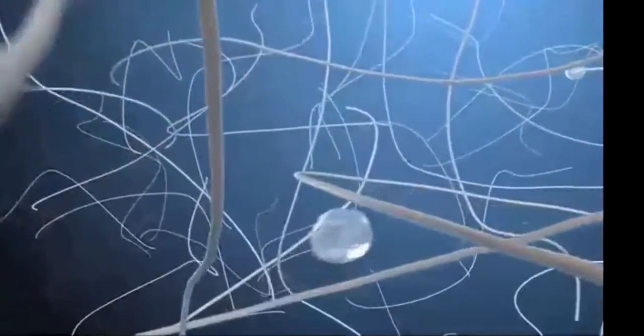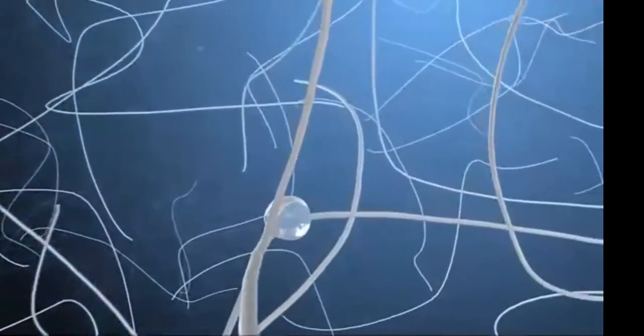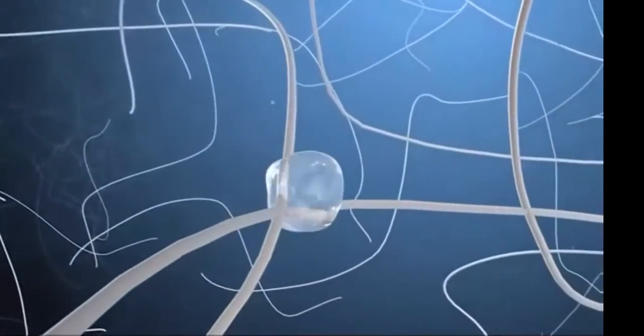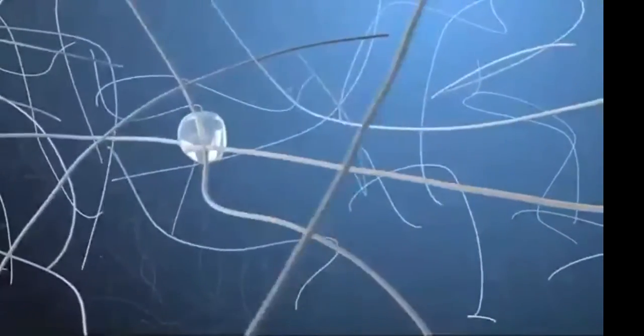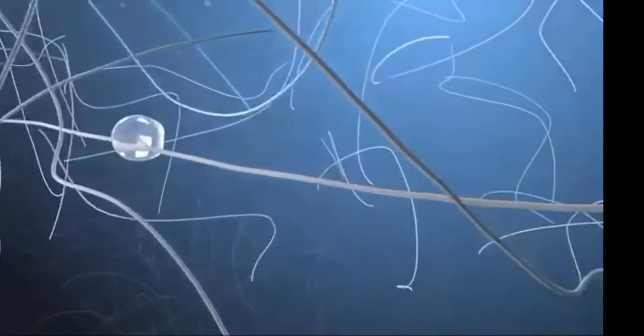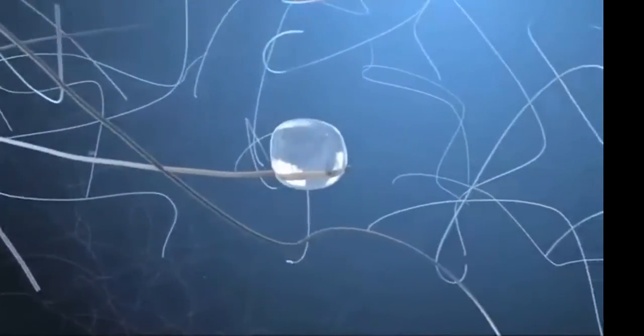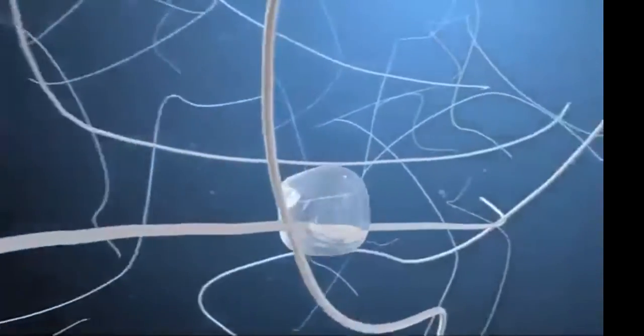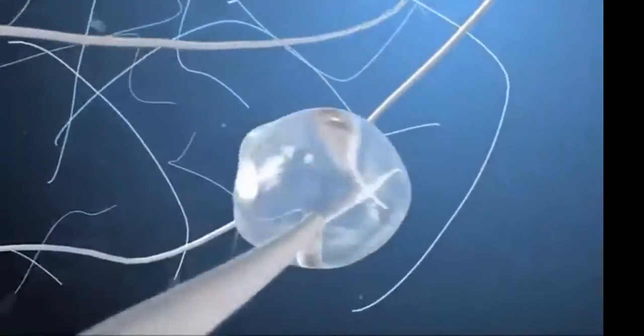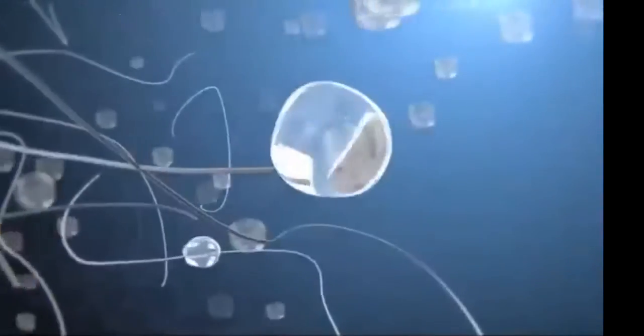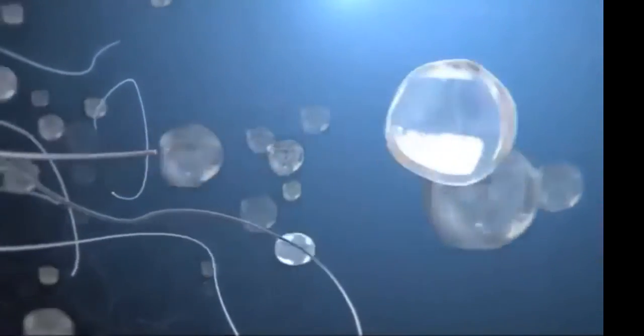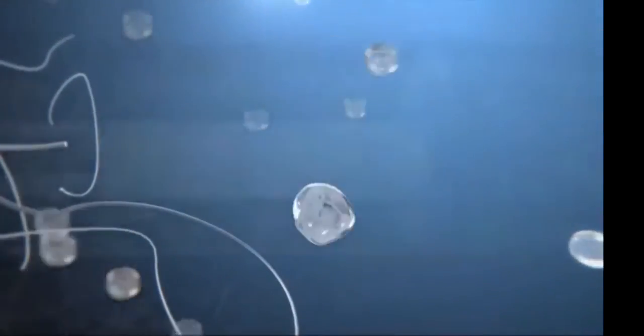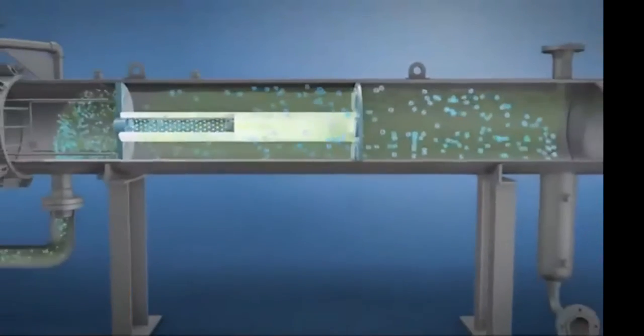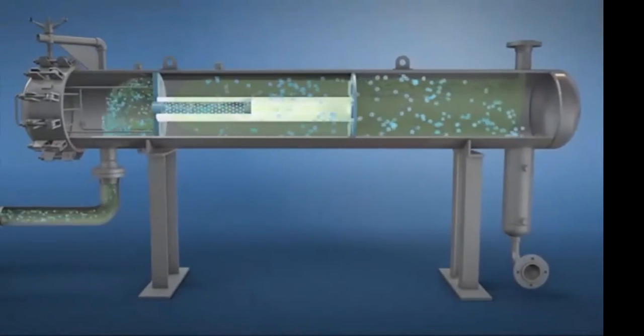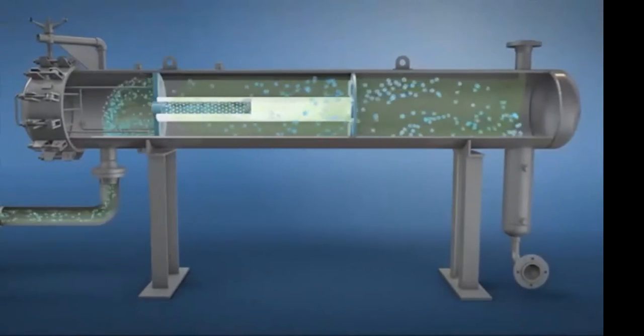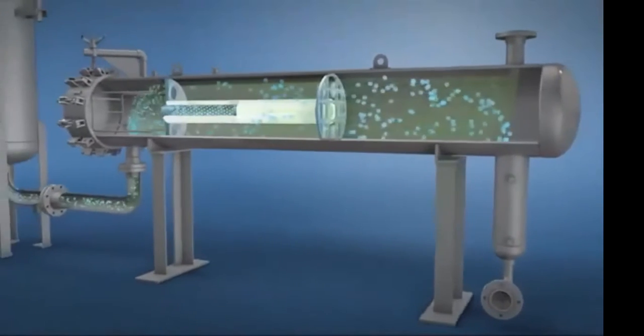The small drops are first captured onto the coalescer fibers where they combine or coalesce. Then, as the drops become larger, the continuous flow causes them to disengage from the fibers. This process repeats itself several times, and the fiber matrix becomes more open as the flow nears the exit side of the cartridge. Finally, the drops leave the coalescer cartridge. The large coalesced drops are then carried downstream and are separated by gravity.